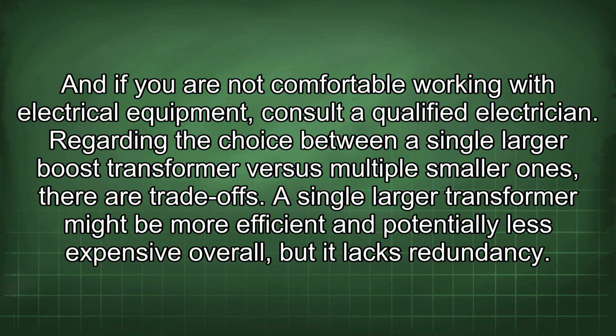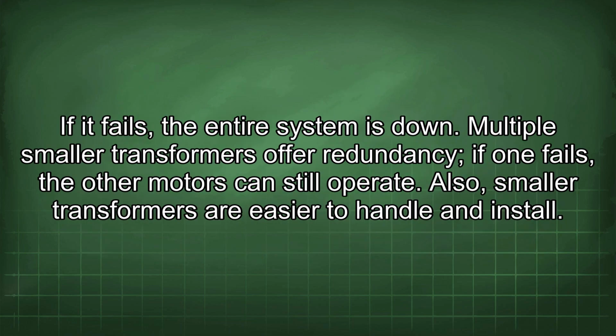Regarding the choice between a single larger boost transformer versus multiple smaller ones, there are trade-offs. A single larger transformer might be more efficient and potentially less expensive overall, but it lacks redundancy. If it fails, the entire system is down. Multiple smaller transformers offer redundancy. If one fails, the other motors can still operate.